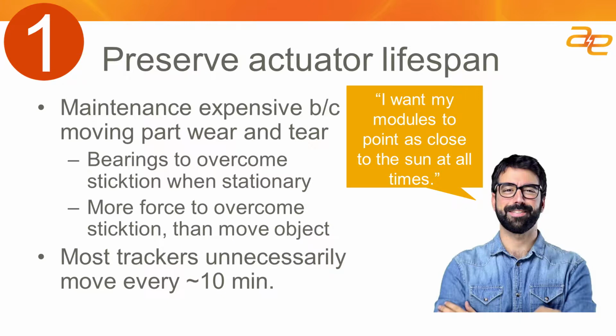So along with the perceived need to track as closely as possible, the downside is just the nature of the mechanical engineering around having bearings supporting the tracker system. Every time you try to move the torque tube, there is a force of stiction where the bearings are trying to stay still and you're trying to force them to move. Overcoming that stiction causes a little bit of wear on the tracker every time you do that. So every time you stop and then start the tracker movement, you're going to have a little bit of wear and tear on those bearings that support the tracker system. Fewer moves means fewer stiction events, which means potentially longer life cycle of the tracker system in general.